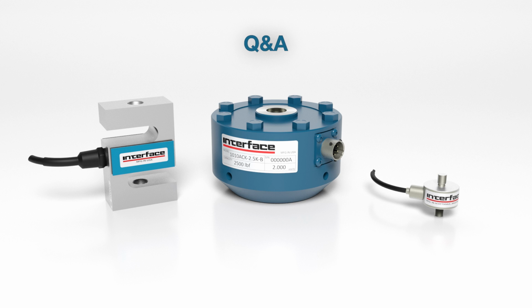Do you calibrate load cells with a 100K shunt by request? We can provide specific shunt cal values. I'd need to check into what the standards are available. I would imagine that if one is supplied, we could also do it in that manner. But again, please feel free to contact us, and we'll run down specifics for you. Typically, I'll just say that we try to scale the shunt cal resistors to be about 60% of the output of the load cell. While we can provide different shunt cal resistor values, usually we have them properly sized for the specific output of that unit to give a good output reading.